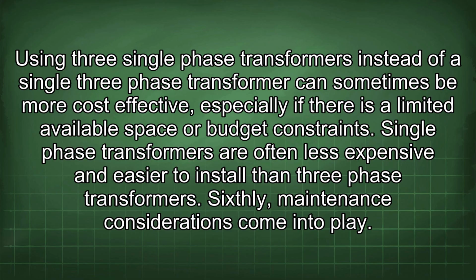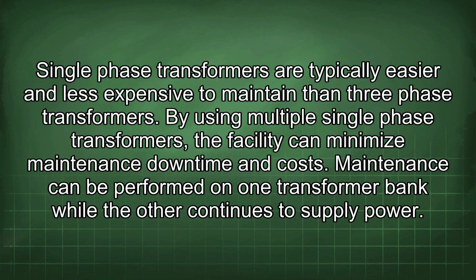Sixthly, maintenance considerations come into play. Single-phase transformers are typically easier and less expensive to maintain than three-phase transformers. By using multiple single-phase transformers, the facility can minimize maintenance downtime and costs. Maintenance can be performed on one transformer bank while the other continues to supply power.